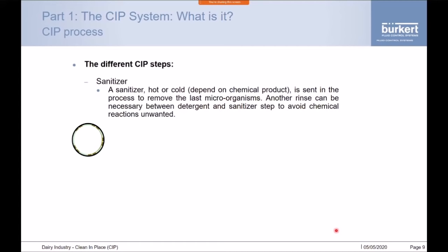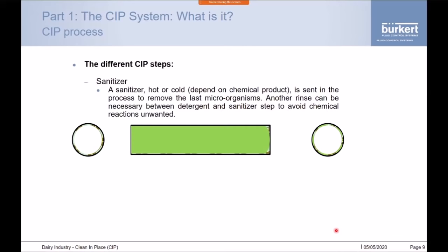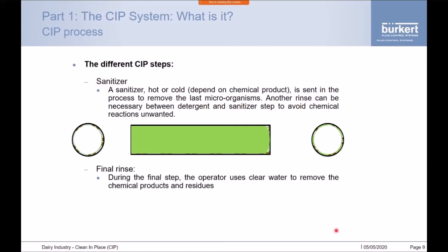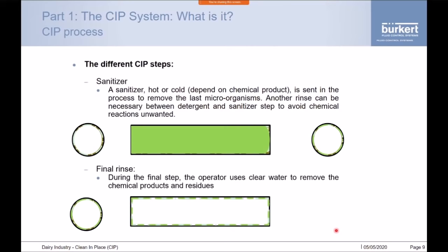Then we move on to the sanitization step, where a sanitization chemical product is sent through to remove any bio-organisms and bacteria and to make sure the pipework is completely clean and sterile. Even after this, we can still be left with a residue of sanitizer, so the final and very important step of the CIP process is to use clean water. Food and beverage companies may recover some rinse water, but the final rinse must be clear water to remove any remaining chemical residue and leave a clean pipe.